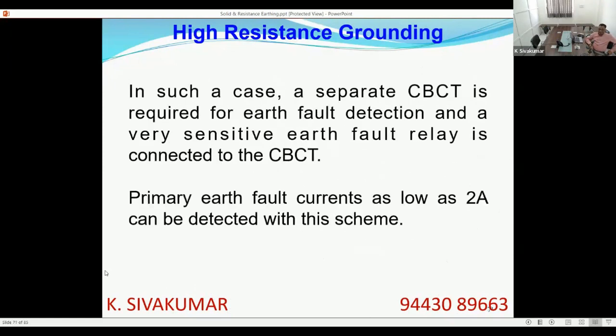You can go for a CBCT. Suppose the current is less than 10 ampere, you go for a sensitive CBCT, earth leakage relay or RCCB, or an earth leakage relay with the CBCT, and set the setting below 10 amperes. A very sensitive earth fault relay, where a primary earth fault current as low as 2 ampere can be detected.